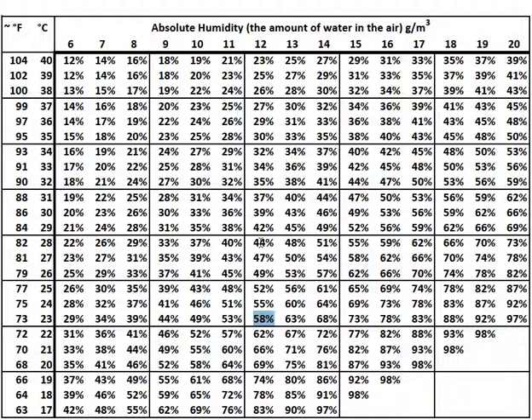So if the outside air is at 44% humidity, we'd get fresh air if we opened the windows, but we wouldn't end up with any drying action. As that air came in, it would cool to the basement temperature or very close to it, and we'd end up with exactly the same humidity. So we're not going to decrease or increase the humidity if the outside humidity is 44%.